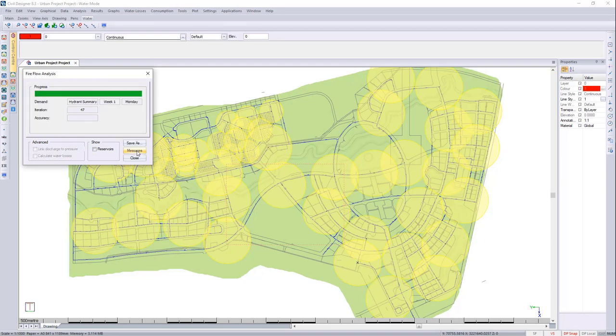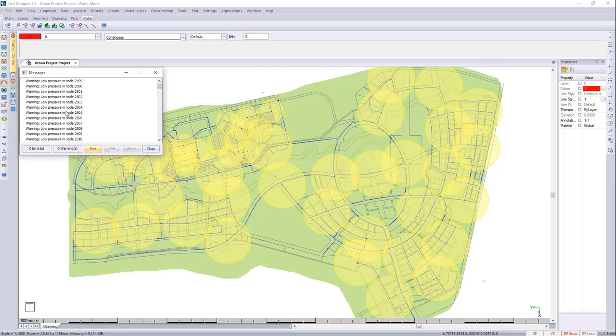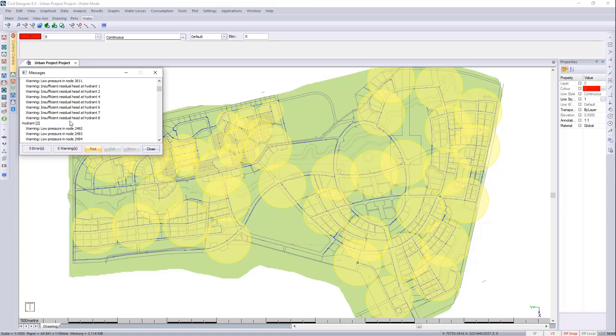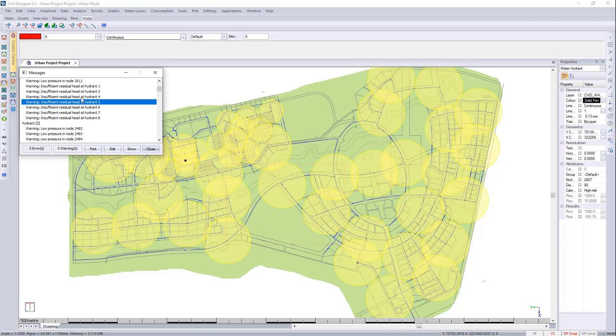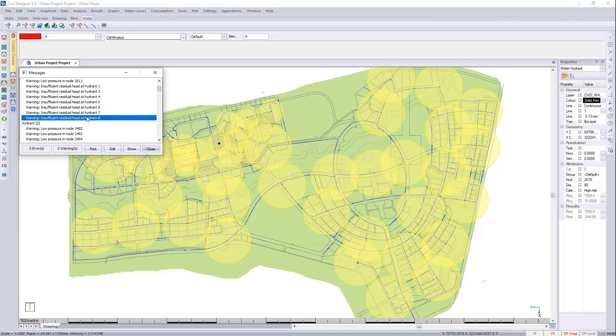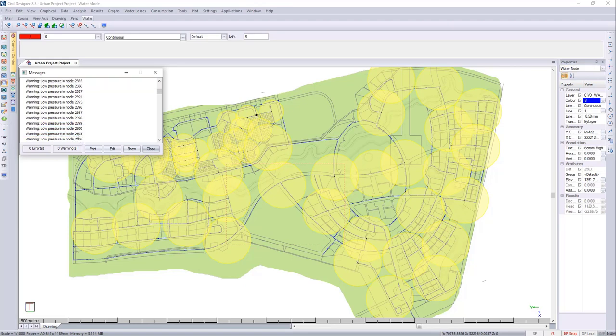We can then look at the messages and it'll bring up that there's very low pressures. So this is something you can adjust with your actual network to these Fireflows. Here you can see you've got insufficient flow at these locations during your analysis. So this is an indication that you need to up your pipe sizes or increase your water coming into your network.